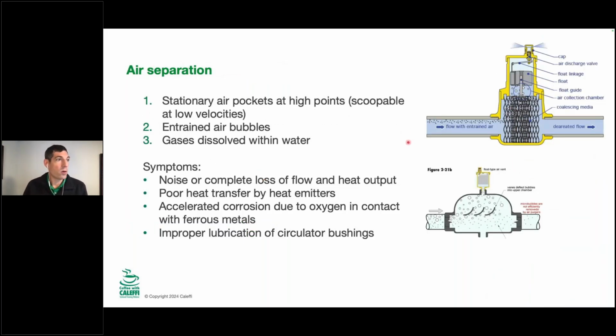Okay, so the air we're trying to separate with these devices: big air pockets, like when you first hook up a garden hose in the summer and you have water then air, big pockets there, most devices are going to catch those. An air scoop like this is going to be great at catching those big pockets of air and sending them up to the air vent. The entrained air, if you filled up a glass of water at your kitchen sink and you see bubbles in there, it looks milky to start, and then it becomes clear as the air bubbles come to atmospheric pressure. Those are the hard ones to get. Those are the ones that will zip right through a scoop style air vent, really. That's what we can catch really well with an air separator, because they're going to hang on those knife edges of the media, gather and become bigger bubbles, and float out the top.